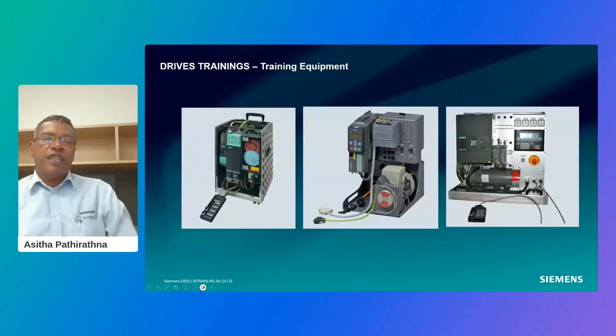The training equipment - in a classroom we can't have real full-scale drives, but we have tabletop drives. It's the same thing, the control unit is the same, only the motors are small and the power modules are smaller. So we have small motors with the same control unit. The controlling, parameterization, commissioning, or troubleshooting will be implemented in a smaller power size drive. The first one in the picture is for S120 servo drive, the second is for G120 drive, and the third is for Siemens DCM. Depending on the training course you choose, we have a different training setup.